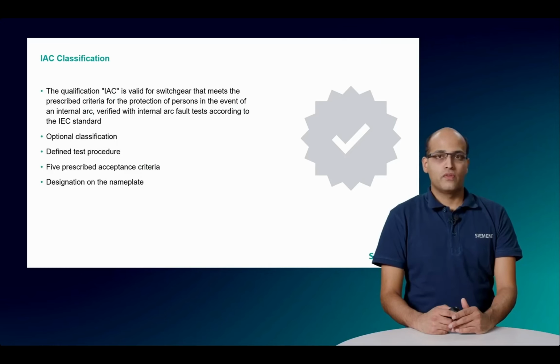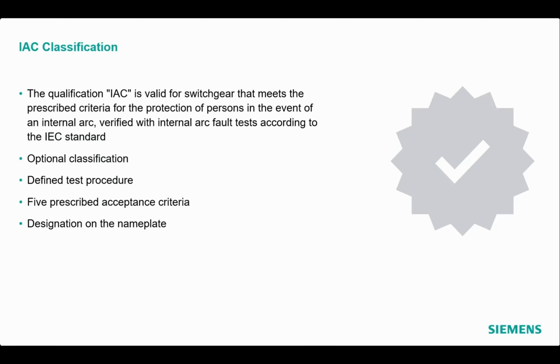There are optional classifications, for example, regarding the arrangement of the switchgear being wall standing or freestanding arrangement. The test procedure to verify the internal arc classification is defined in the IEC standards. There are 5 prescribed acceptance criteria to pass the test. If IAC classification is assigned, then this designation is included in the nameplate of the switchgear.